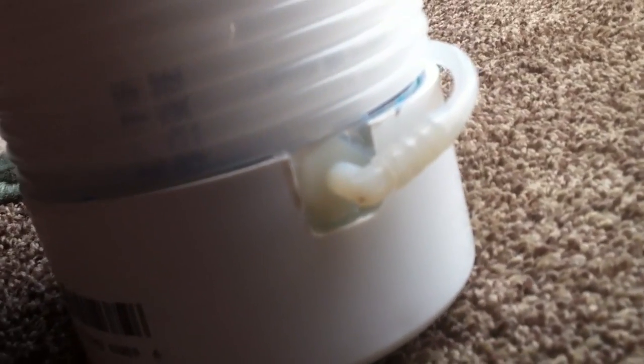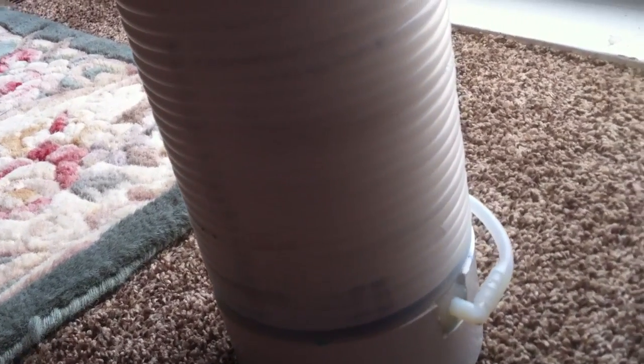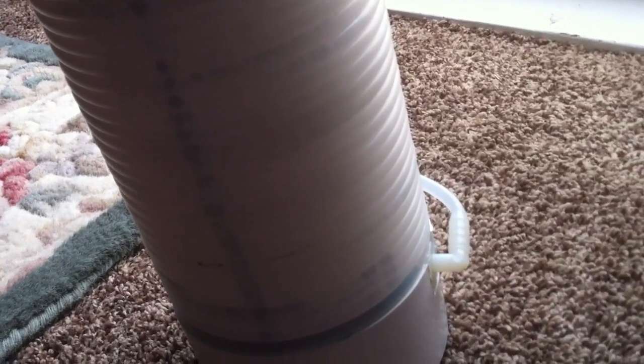The Teflon failed. That seems to happen quite often with PVC when you're threading on a union like that with PVC or anything like that. It's pretty much hit or miss with the Teflon. If the Teflon gets jammed on something, it just spins through the threads and doesn't go all the way down into the actual threading. It just gets spun off the union you're screwing in, and then it just piles up on the top. So then you're basically screwing it in without anything.